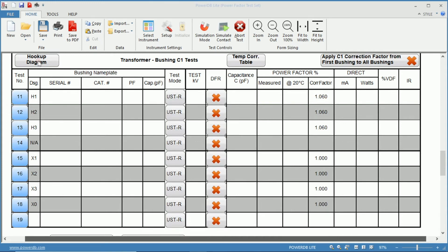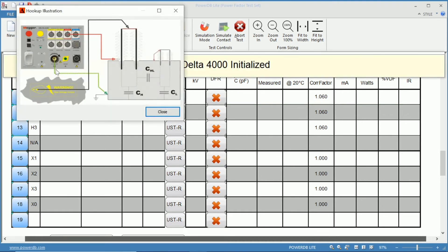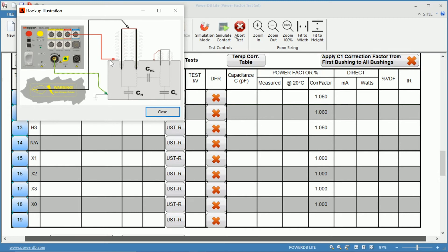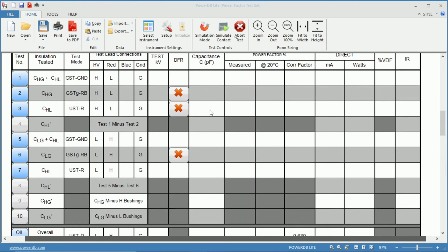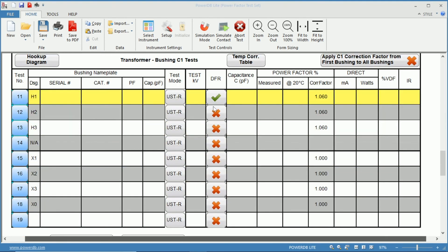There is a hookup diagram for the C1 test as well. If we hit the hookup diagram, we can see we are applying voltage on the high side bushing, measuring from the C1 tap, and grounding based on the transformer ground. Just as we have the ability to run the narrowband DFR in the transformer tests, we do in the bushing tests as well. Here we are able to perform the narrowband DFR if selected.